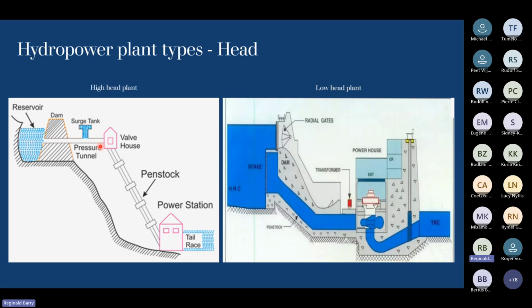Before you go into the penstock or high pressure pipeline, you take it through a valve house where you control the flow, and then into the penstock, and then down at high pressure. As you go down to the powerhouse, the pressure increases more and more. Then in the power station, you take it into a turbine. The turbine drives the generator, the output terminals feed switchgear, and then typically step-up transformers, and onto the network or the distribution line. So that's a typical high head plant.